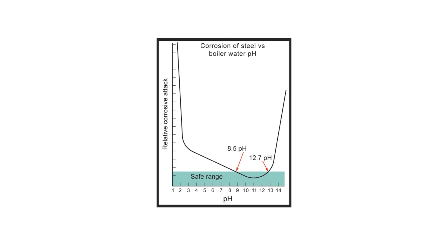Boiler water with a high pH can also be corrosive to metal exposed to the alkaline water. This corrosion results from the direct reaction of the hydroxide ion with the passivating magnetite layer, thus removing the protection of the magnetite layer. The unbalanced reaction is shown here: hydroxide ion plus Fe3O4 (magnetite) goes to FeO2 (ferric oxide ion) plus water. Continuous operation of a boiler with alkaline water will result in caustic corrosion, which causes generalized corrosion or severe localized gouging of the boiler metal, sometimes called caustic gouging.